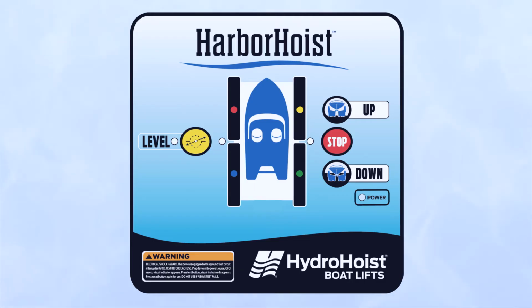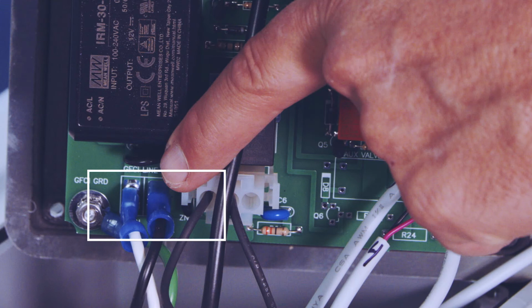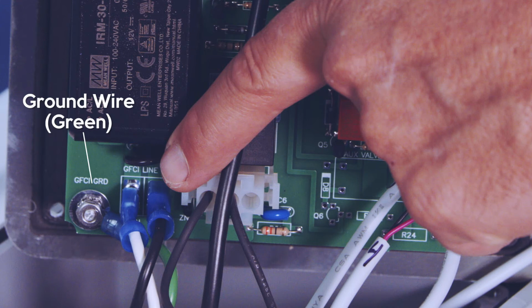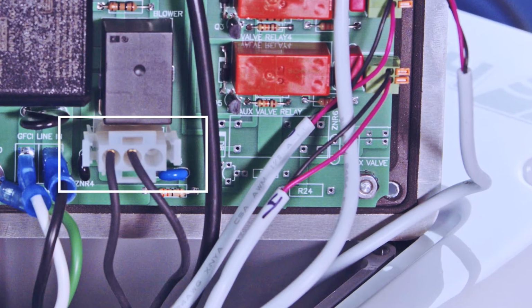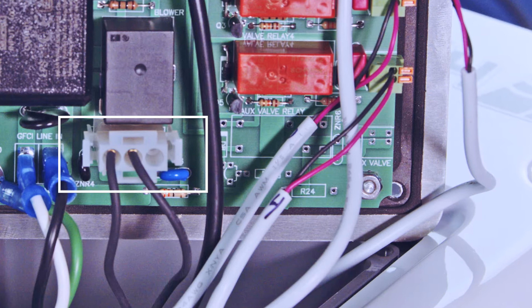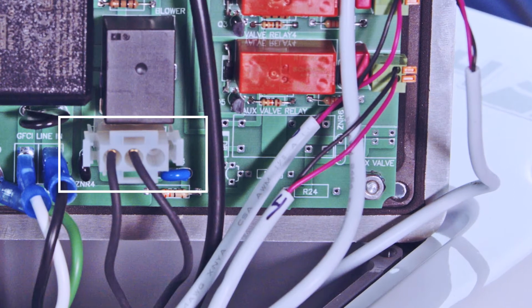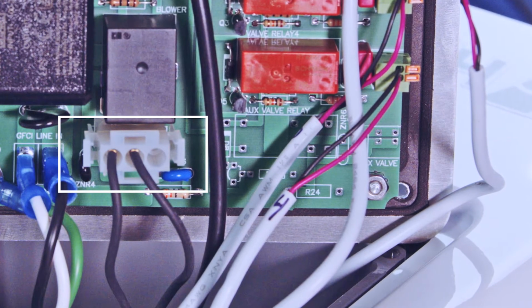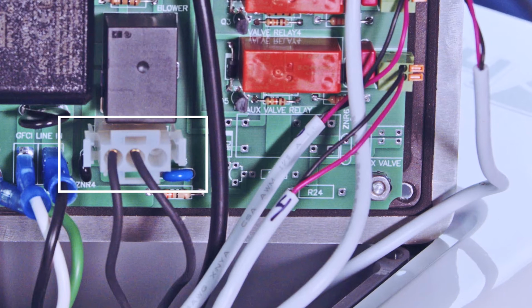Main control module replacement. Insert spade connections for power lines and tug on them to verify that they are on properly. Connect ground wire and screw nut down. Push the white blower power connector back on to the connector on the board. You should hear a slight snap indicating it's locked. Tug on it to verify it is secure.